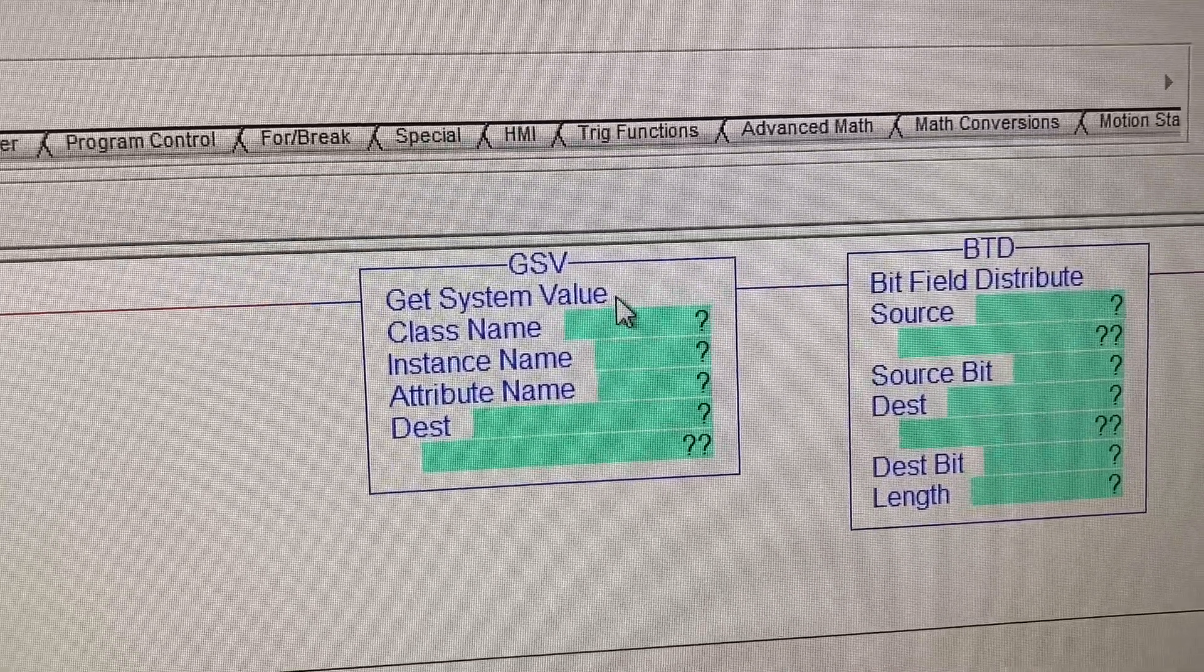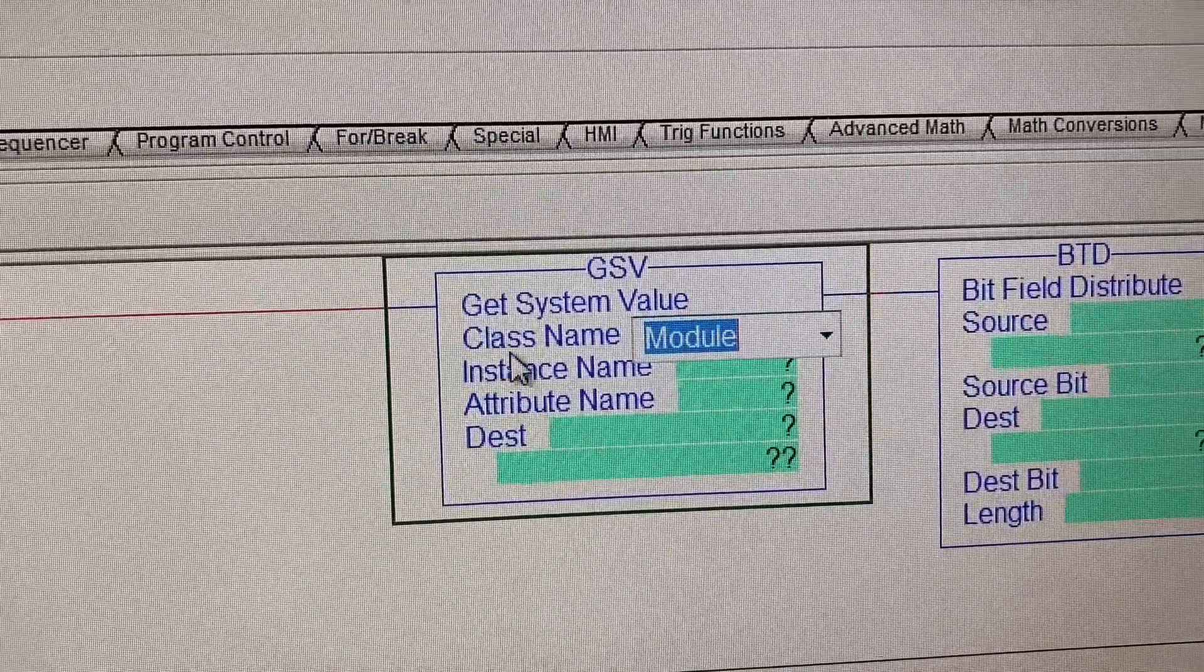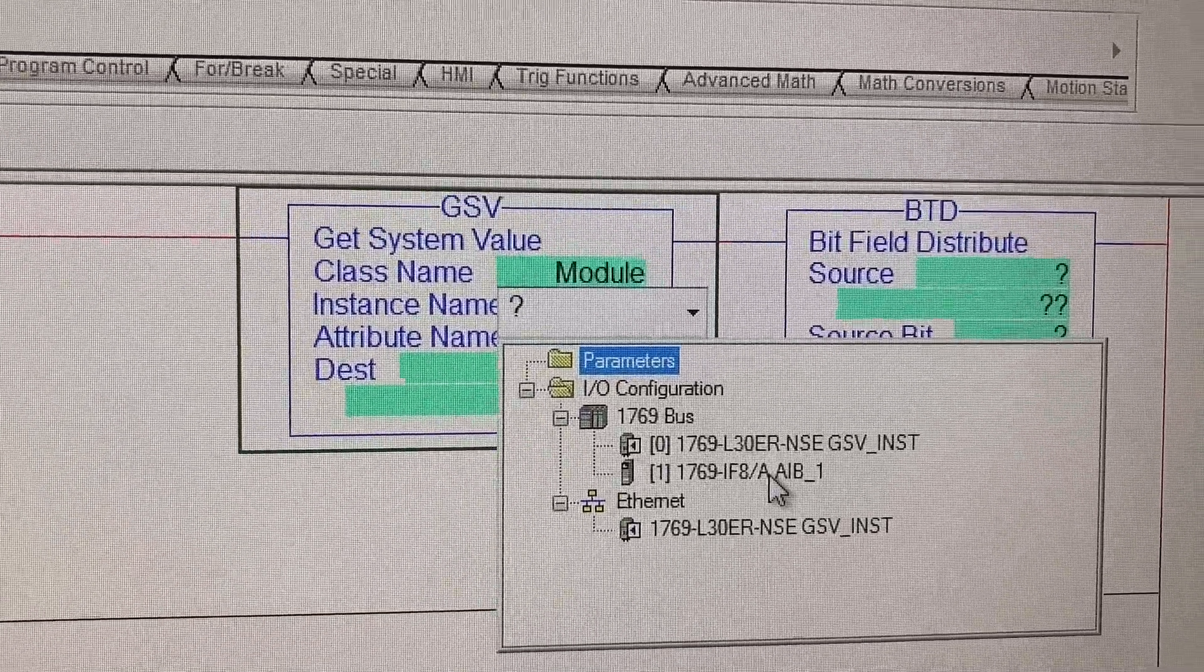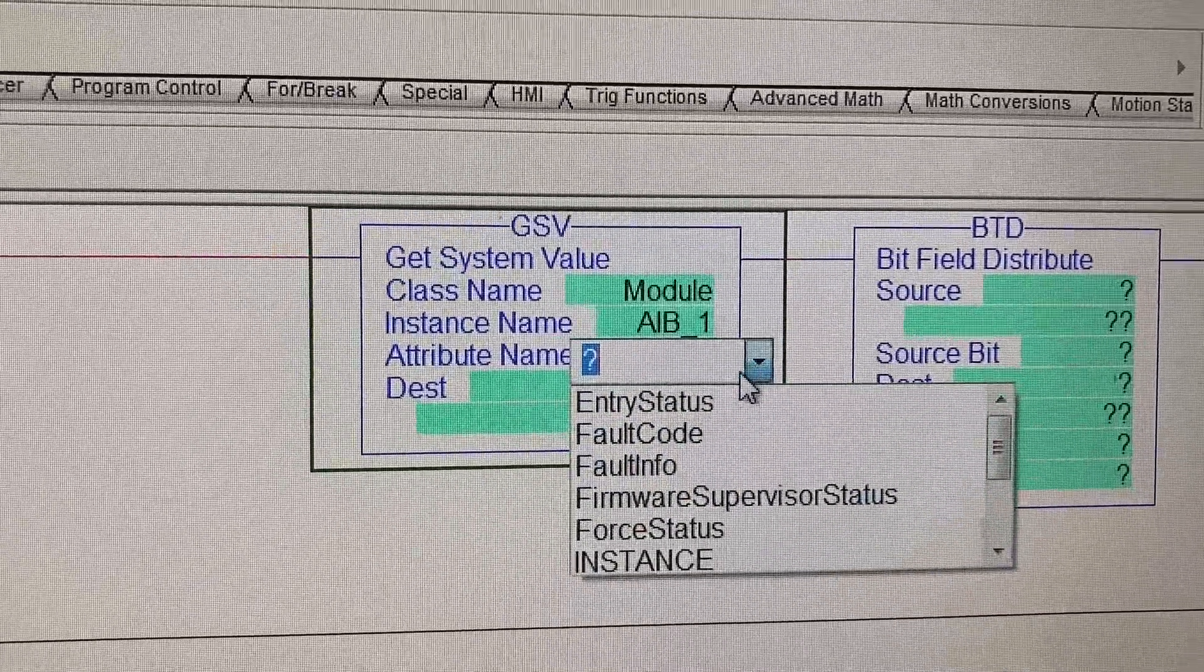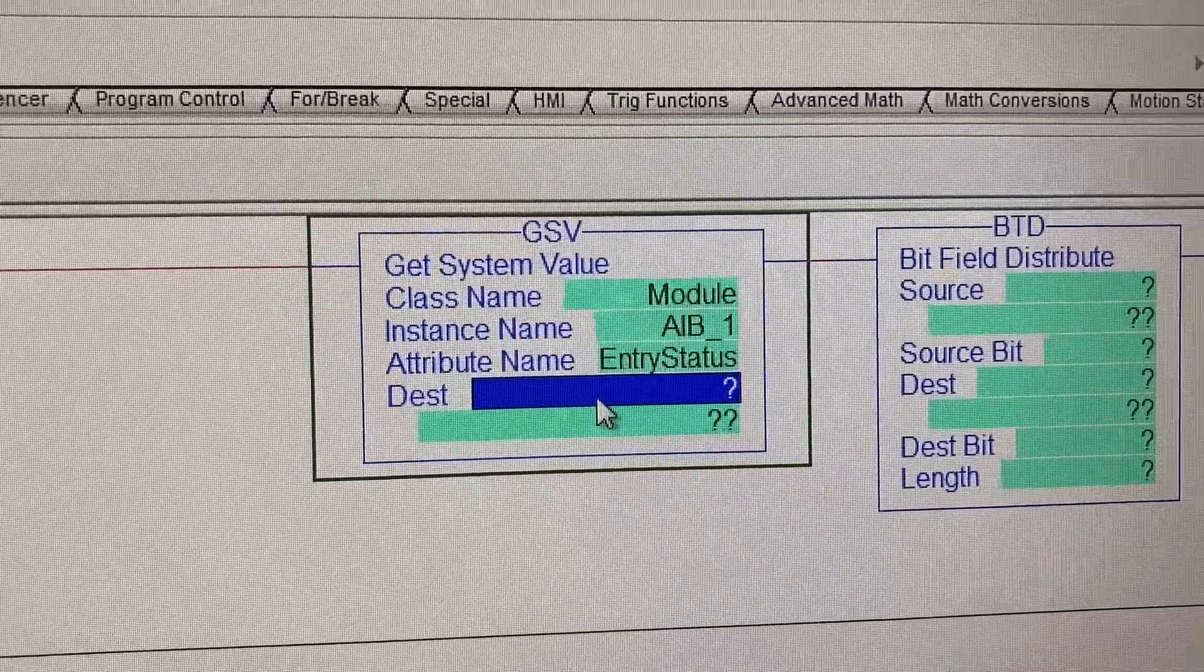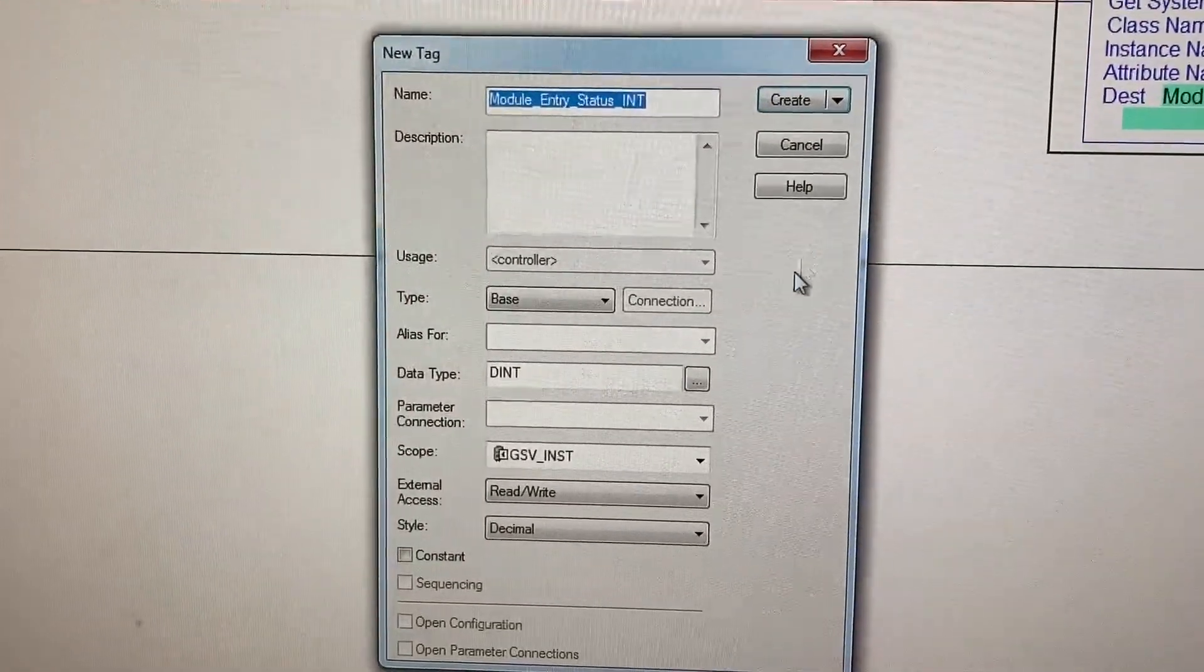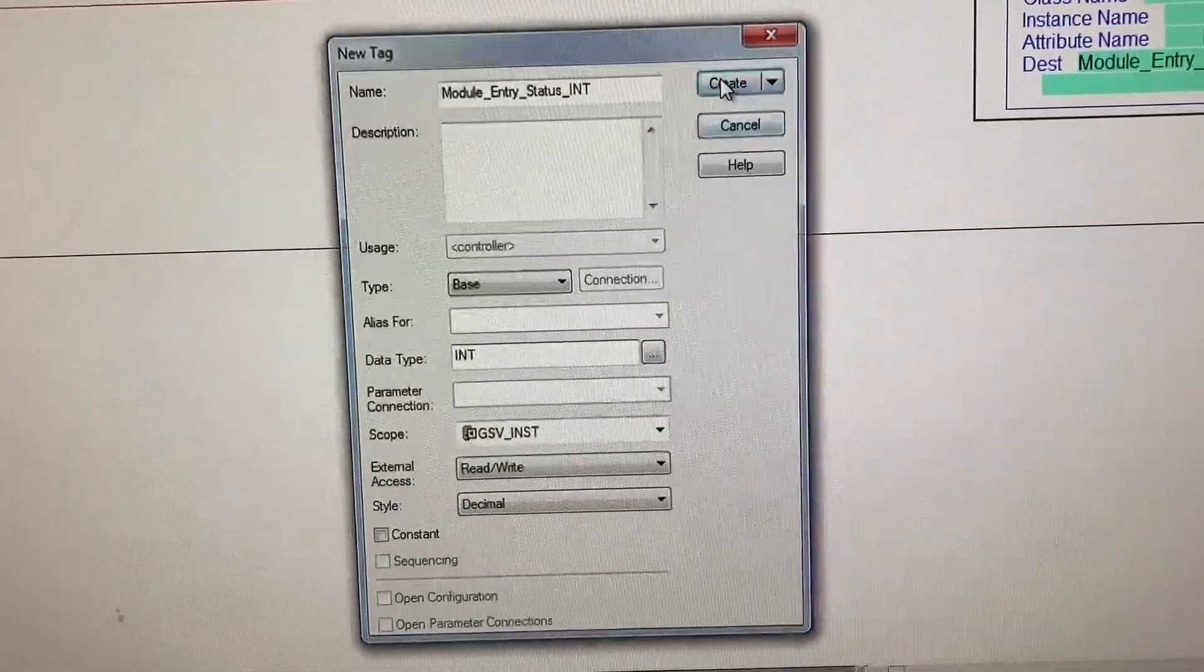For the GSV instruction we will have Module for the class name, instance name will be the analog input module, attribute name will be Entry Status. Destination will be a tag in integer data type. Right click, new, change data type to integer 16-bit, create.